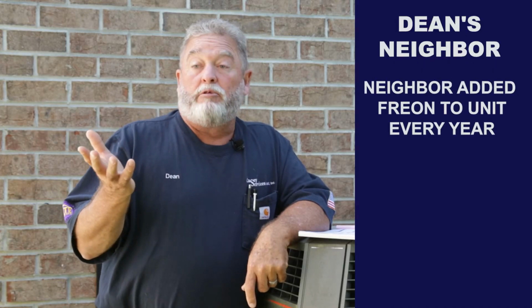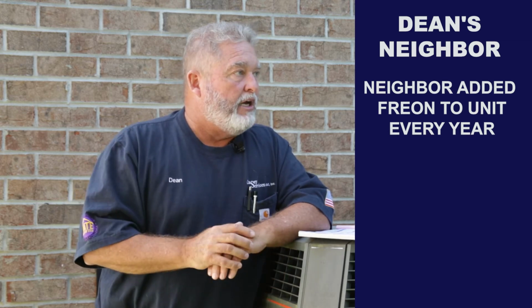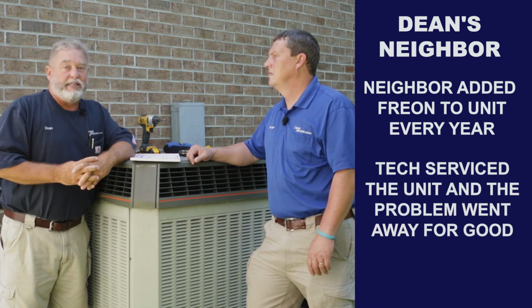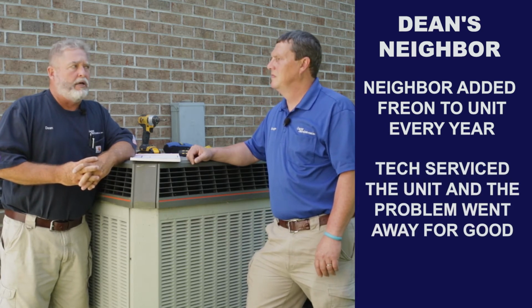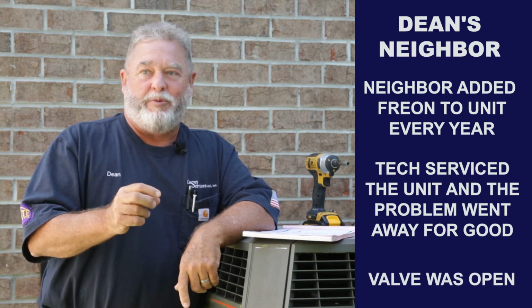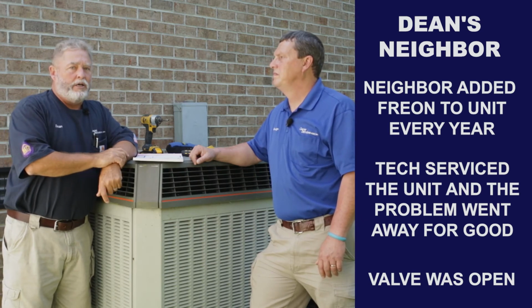I'll give you a perfect example. Up at the lake, I had an elderly lady across from our lake house who every year had to get Freon in her unit. So I took one of your techs up there and checked it out. For the last 3 years, she hadn't needed Freon anymore. Your tech found that the Schrader valve was loose and the little cap was left loose. So if you don't have a reputable heat and air company looking after your best interest, a sorry or crooked tech could actually let Freon slip out every year.